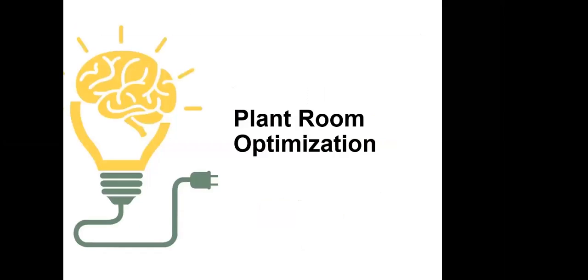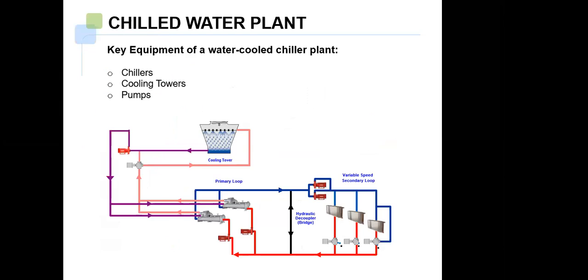So I will straight away now jump to the plant room optimization. This is a typical schematic of a chilled water plant room. Today I will be talking about basically three key components in the plant room. One is the chillers, which are the most power consuming equipment in the plant room. Second is the pumps, the circulating pumps which circulate the water throughout the circuits, throughout the building. And the second set of circulating pumps are the pumps which are rejecting the inside heat of the building to the atmosphere.